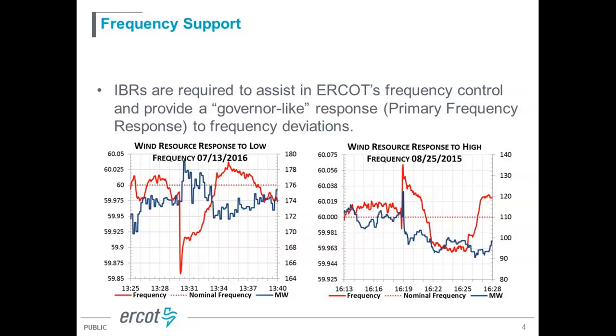Something we'd like to highlight here is that currently the IBRs connected to ERCOT are required to provide frequency support when they have headroom. They are not required to keep headroom unless they participate in the ancillary service. So typically, if a project always operates at the maximum output at the time, it likely may not have enough headroom to increase output, and as a result doesn't need to provide the support. However, during some conditions, as an example during constraints, they operate below the maximum output, they have headroom, and they are required to respond to the frequency.